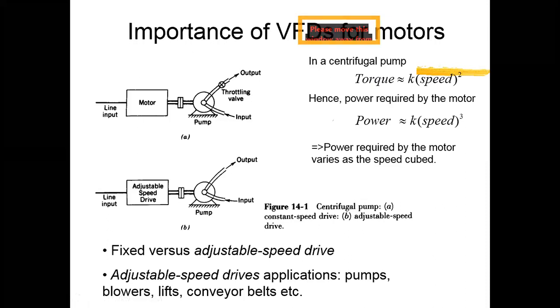Speed squared, right? The flow rate is proportional to the speed of the pump, and speed of the pump means speed of the motor, and the power is the torque into speed, basically, right? Power is torque into speed. Is the torque proportional to speed squared, and the power speed cubed, you can see. So the power supplied by the motor is proportional to speed cubed.